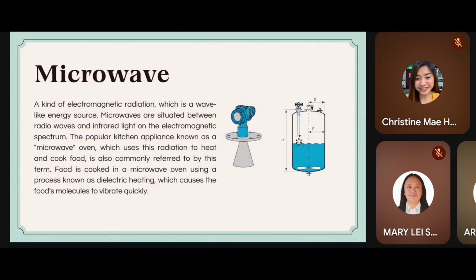Now, as for the microwave, the main principle of microwave level measurement is very similar to ultrasonic, but instead of sound waves, it uses microwaves. Microwaves bounce off the material surface, and the reflection time indicates the level. So, of course, it has its advantages. Mainly, it works well in harsh conditions such as high temperature, high pressure, and presence of vapor or inert gases. As for its applications, it is continuous, non-contact measurement of liquids, paste, and slurries.